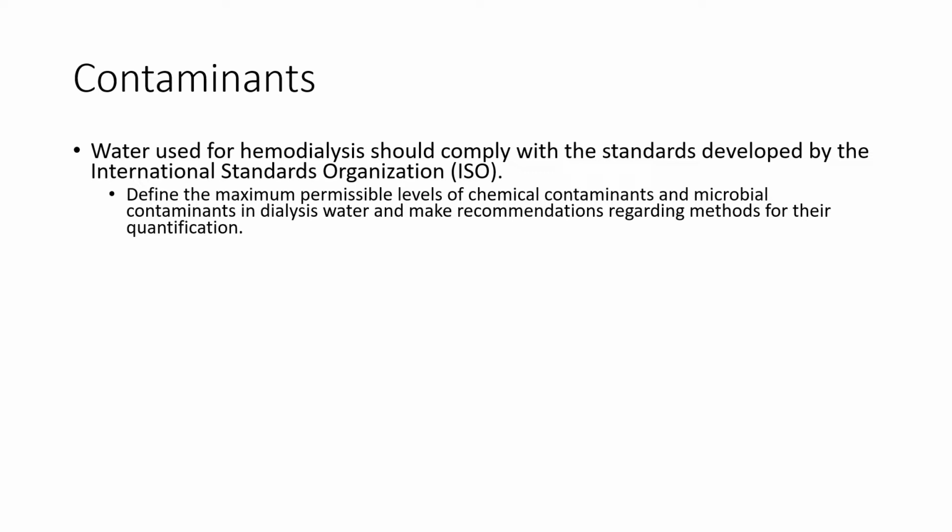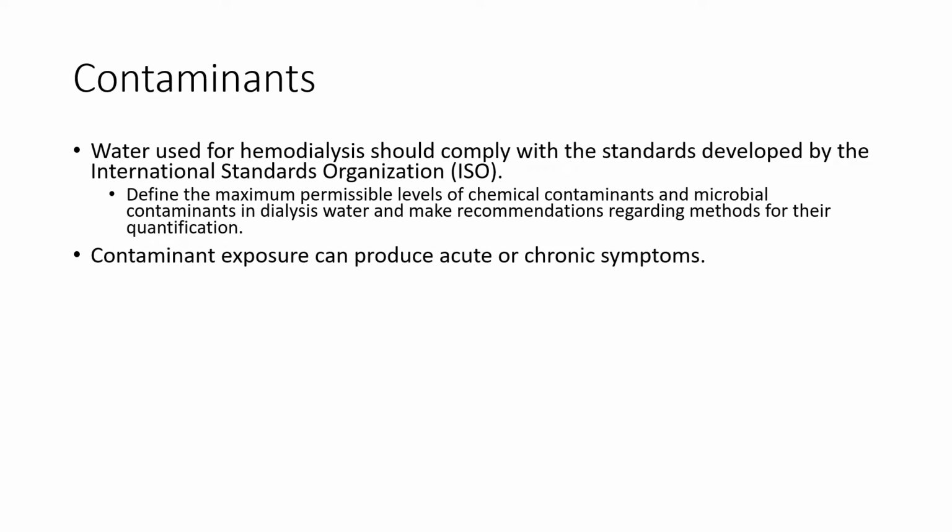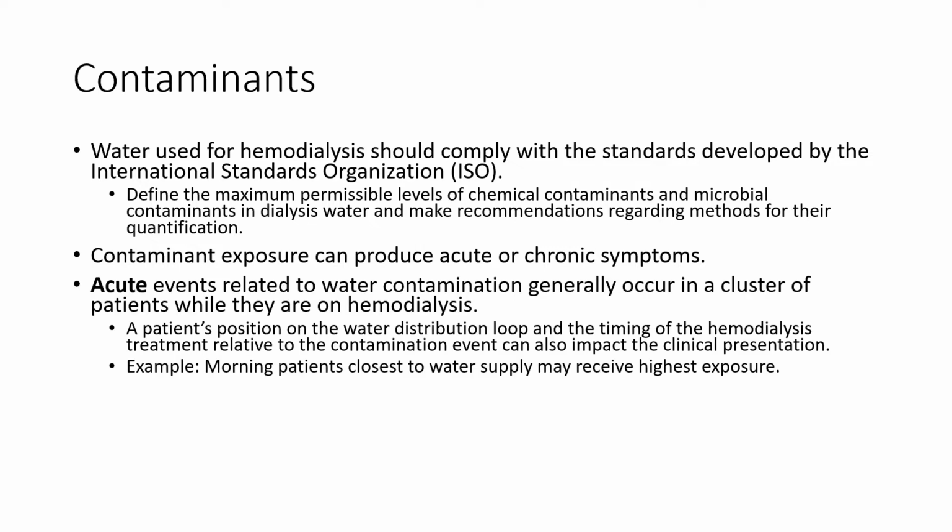These standards define the maximum permissible levels of chemical contaminants and microbial contaminants in dialysis water and make recommendations regarding methods for their quantification. Contaminant exposure can be associated with clinical manifestations that are either acute in onset, so say happen at the time of exposure, or that develop over time with chronic exposure.